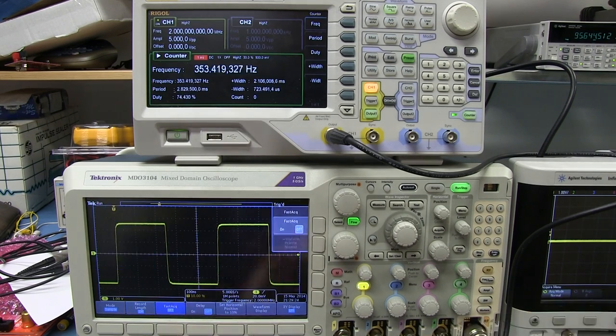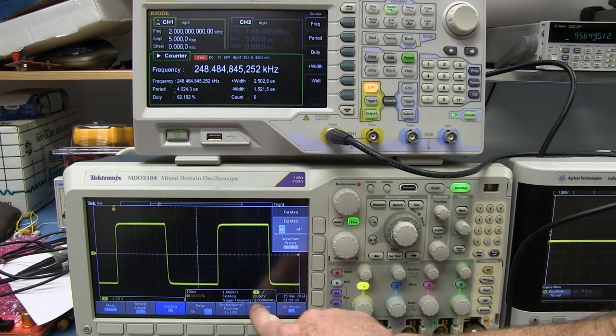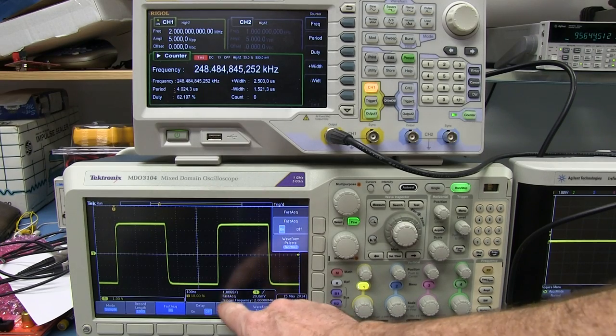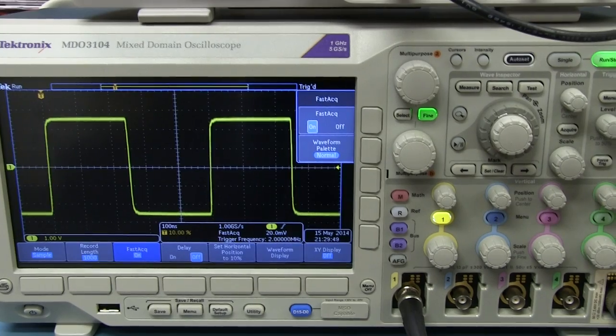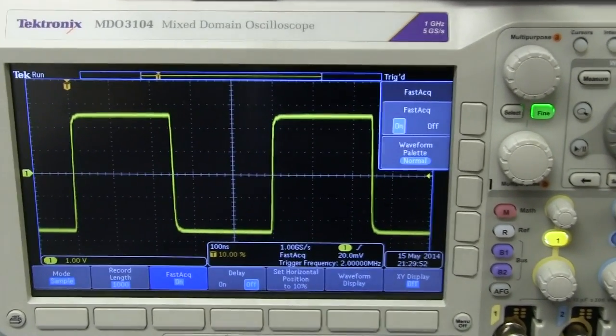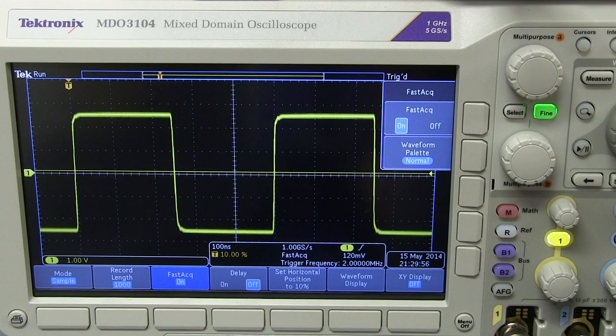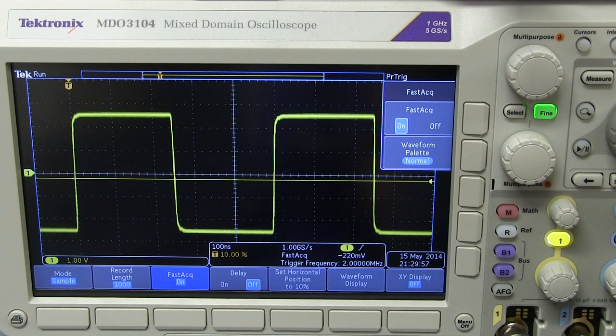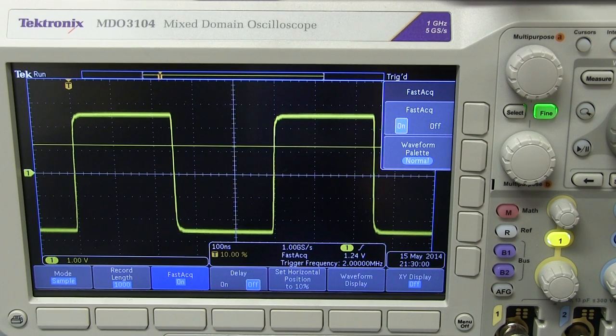If you turn fast acquisition mode back on, we're back up to 250,000 waveform updates per second. That's at 100 nanoseconds per division. But watch what happens if I change the trigger level - here's my trigger level, right in the middle here.